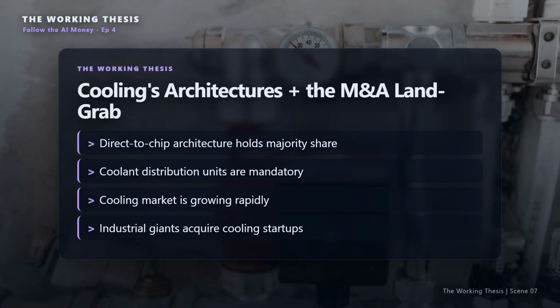Let's break down the architectures. Cold plate, or direct-to-chip, commands a 65% market share. Coolant-filled copper plates are mounted on the chips, embedded directly by OEMs like Dell, HPE, and Lenovo. Immersion cooling submerges the server in non-conductive dielectric fluid. It's the most efficient, hitting a PUE of 1.02 to 1.05, but remains a niche for ultra-high-density setups because of specialized tank infrastructure. Regardless of the architecture, you need CDUs, coolant distribution units, to pump and regulate the fluid.